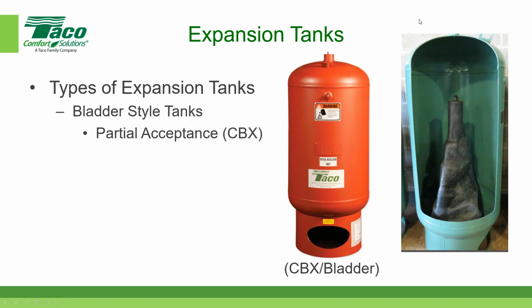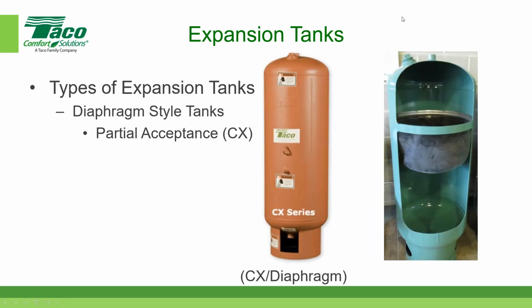Okay, so now let's go to the last category. And the last category is called a diaphragm style tank. Again, we're looking at the steel container. You can see there's lots of things that are common. There is the collar at the top that holds the Schrader valve. There's the air side of the tank. And the water comes into the bottom. You can actually see the connection on the left here for the piping connection on the bottom. And in this case, it looks like a rubber bowl, and we call it a diaphragm.